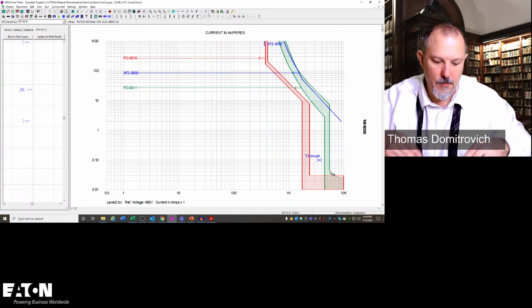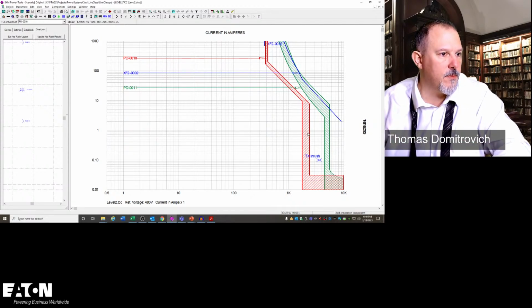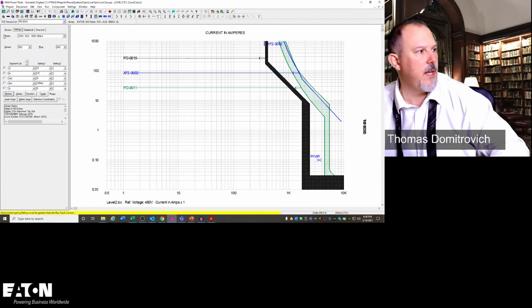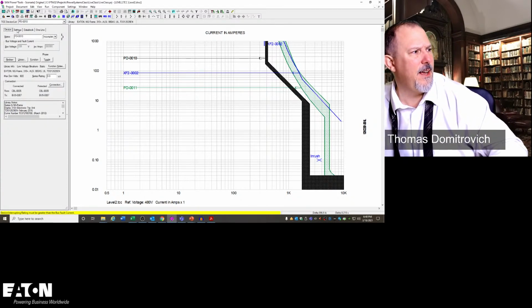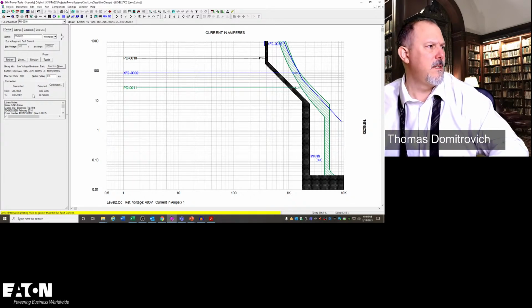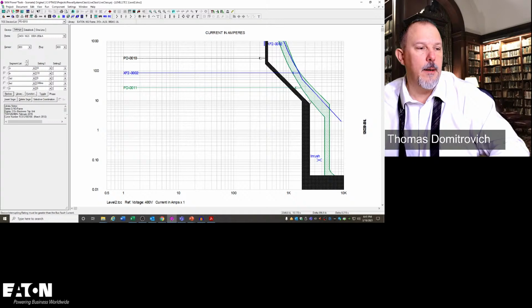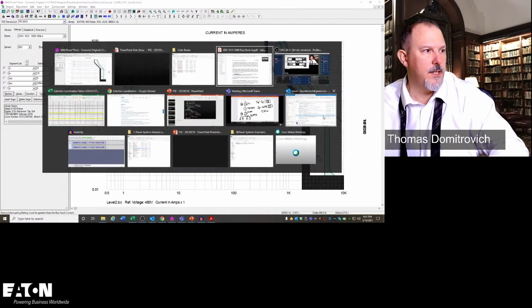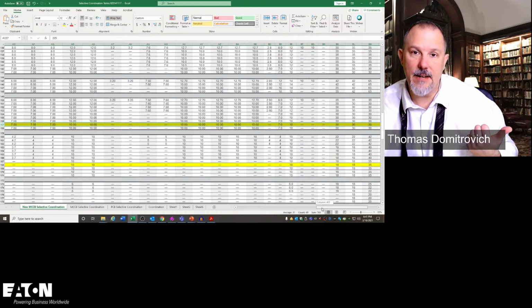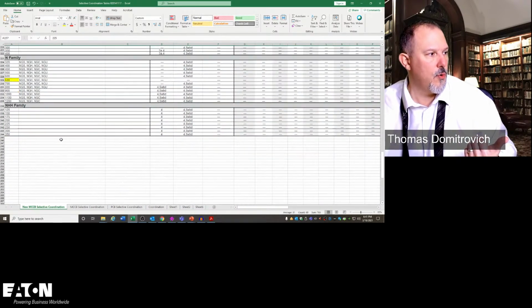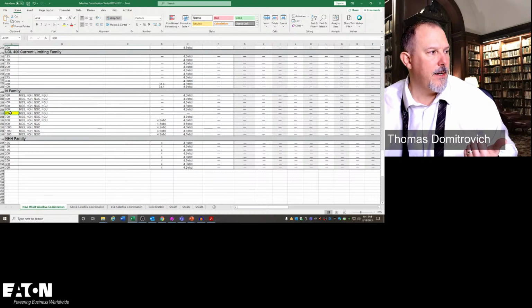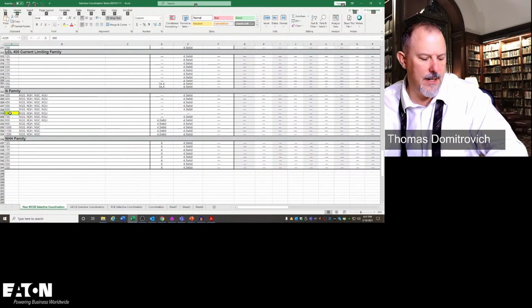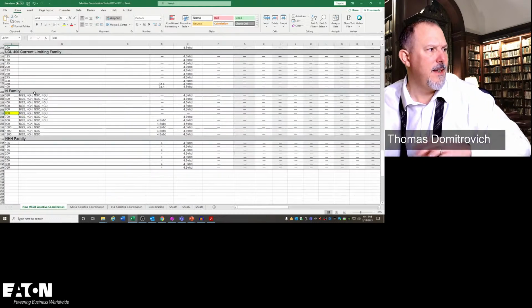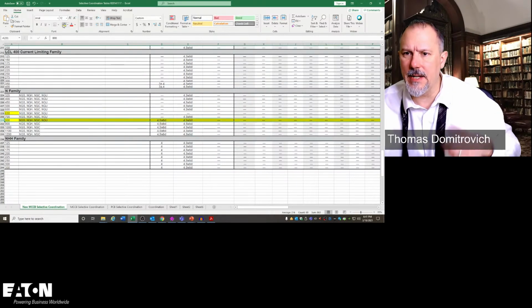So when I go into the tables, what's my downstream device? Oh man, what is it? It's an NG breaker. It's an N frame breaker, right? So I can go into this table on the left-hand side because the downstream is an N. Just scroll down. There's my N, and it is a what? Was that my 800 amp breaker? Yes, it's an 800 amp breaker. So there's my NG breaker, right?